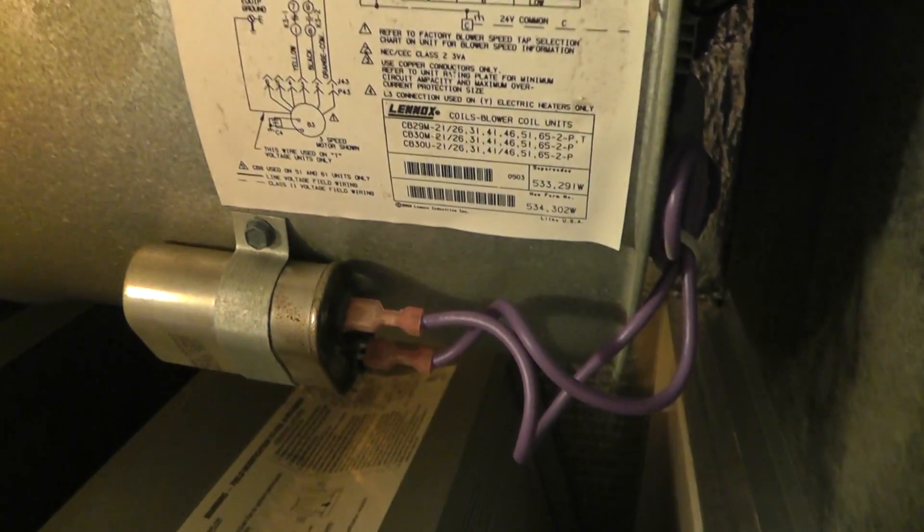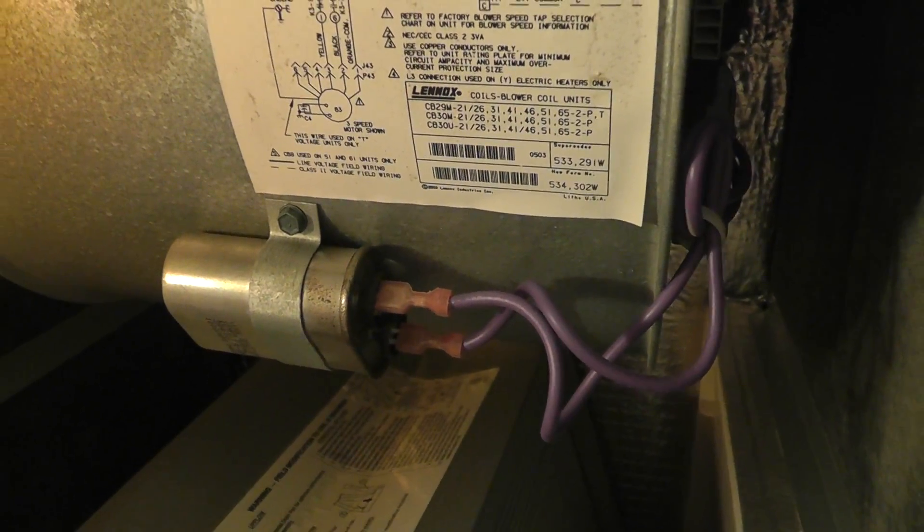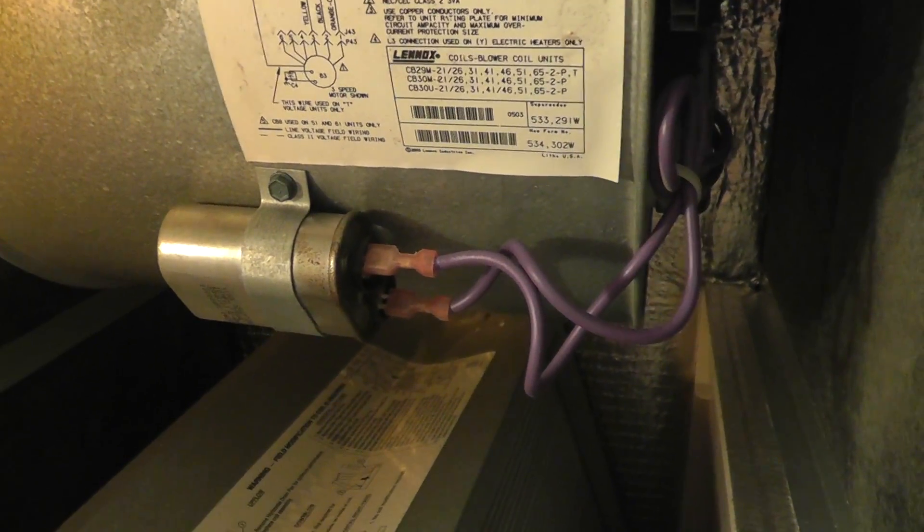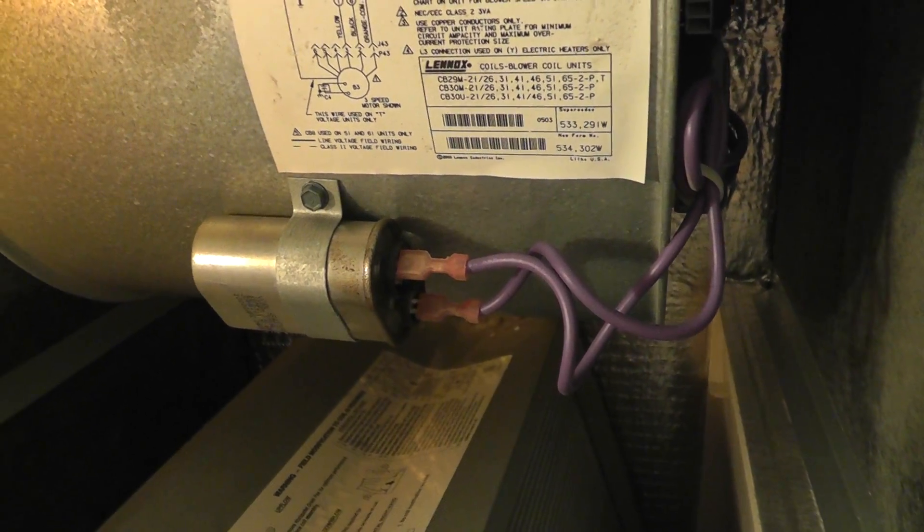and then we want to discharge this run capacitor by touching those two terminals together to discharge the run capacitor. We take the leads off. We can measure it with our multimeter on MFD, or you might just look at it and see its bulge or some jelly or goop coming out of it, and you know the run cap's bad.